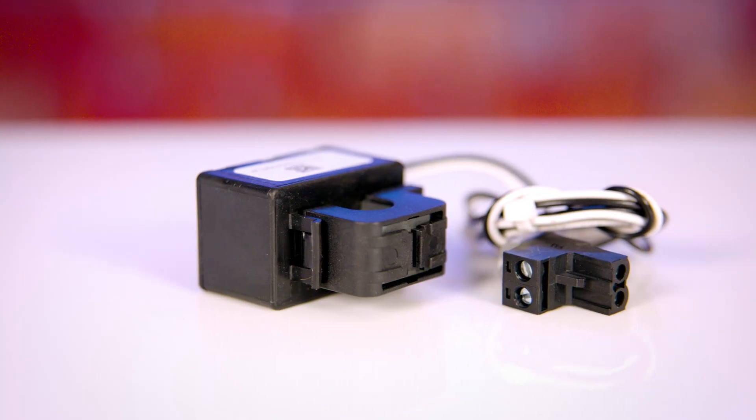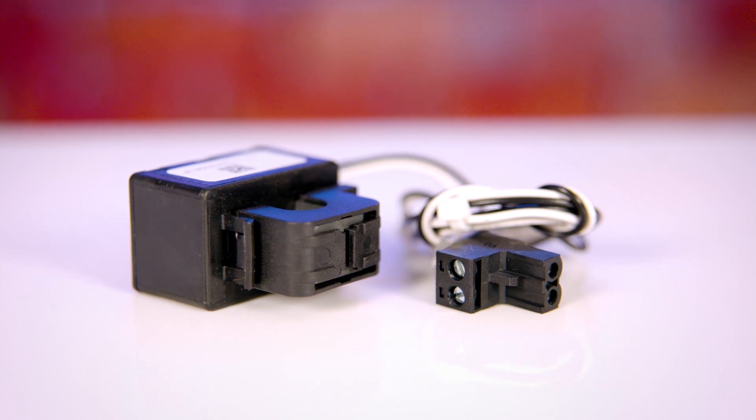I'm going to do a quick unboxing and then we can talk about the features of the Victron variant versus the Carlo Gavazzi, just to see whether it might be a more appropriate choice for your particular application. The part number is the VM 3P75CT — 3P for three-phase and CT for current transformer. The current measurement is done by current clamps, so this is principally a three-phase monitor, but you can just clamp one phase if you've only got a single-phase system.